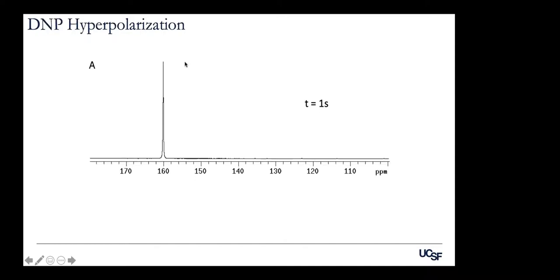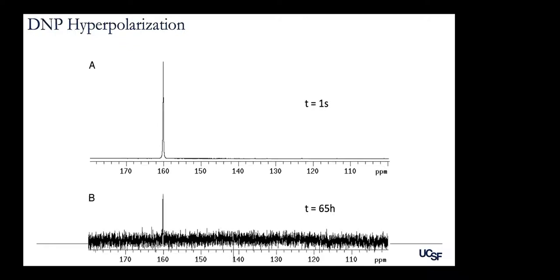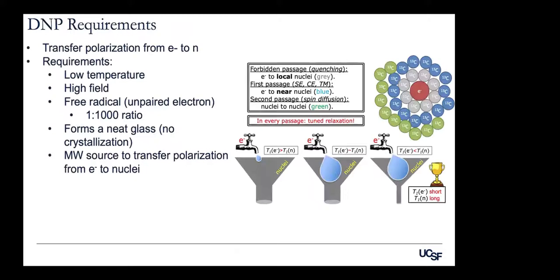In practice, a small amount of hyperpolarized urea goes into a Hypersense polarizer, builds up for an hour, and is then dissolved. A single spectrum scan with a 90-degree tip angle and one FID gives a dramatic result. Comparatively, putting that sample into a 9.4 Tesla magnet at Boltzmann equilibrium would require 65 hours of averaging at the Ernst angle to obtain a comparable result. This dramatic increase in signal-to-noise allows experiments that would otherwise require inordinately long averaging times.